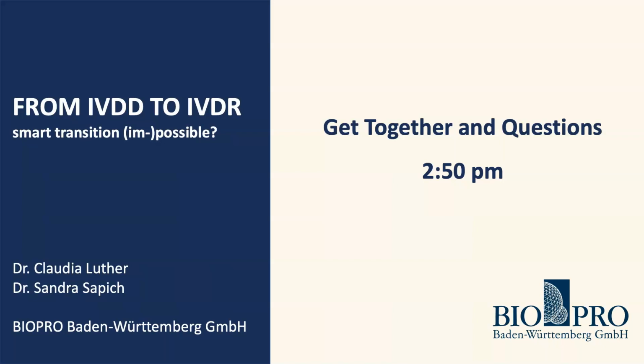So who knows a problem, or who would be able to trace a problem to the device if something bad happens? There is an agreement between the OEM, so the original manufacturer, and the legal manufacturer, the PLM, for support. But under the regulation, you have as the legal manufacturer, if you put your name on it and you register in EUDAMED this product, you have to have access to that technical file, meaning the full technical file according to Annex 2, and meaning that the data needs to be there in your hands.